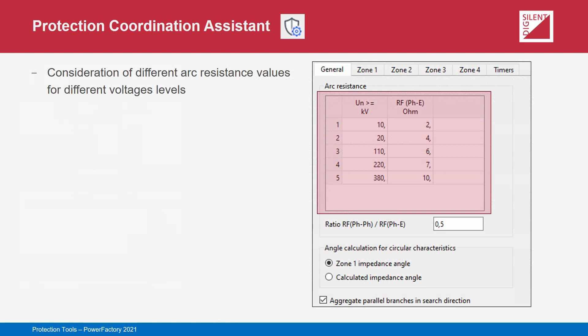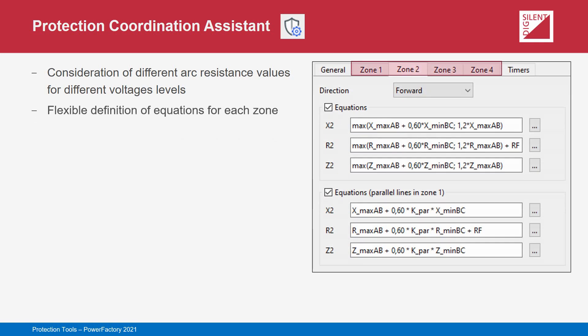The definition of setting rules needs to be flexible enough so that different users are able to recreate the coordination rules they need. For the calculation of resistive reach, an arc resistance must be assumed. PowerFactory allows the arc resistance to be specified and selected based on the voltage level at which the relay is located. Different arc resistances can also be specified for line-to-line resistive reaches as compared to line-to-ground resistive reaches. The equations are defined as text using keywords which pertain to minimum or maximum impedances of lines or cables to construct the equations.